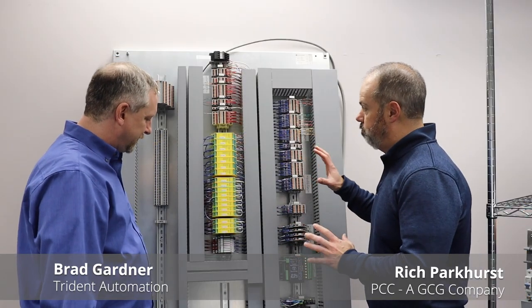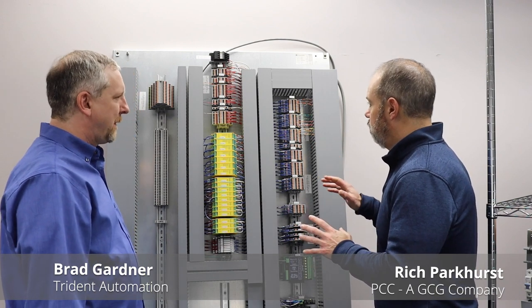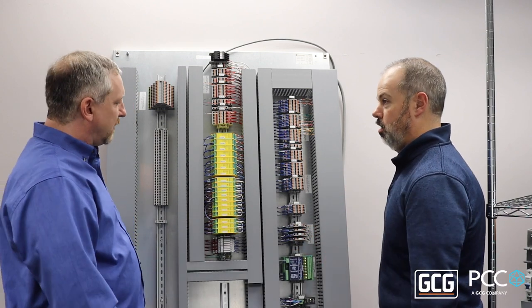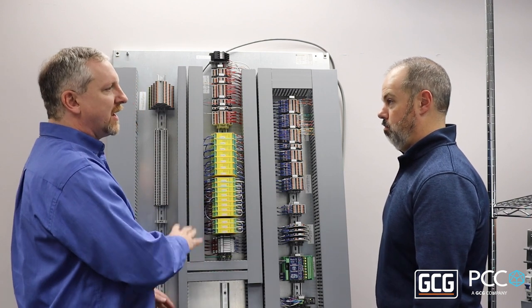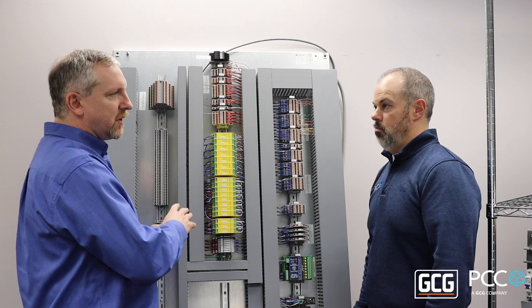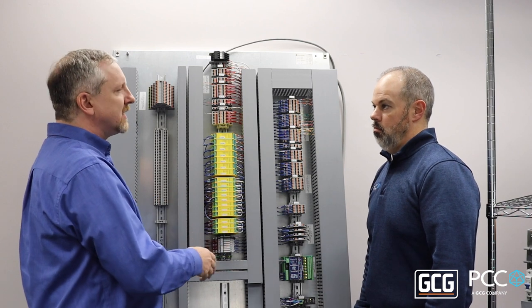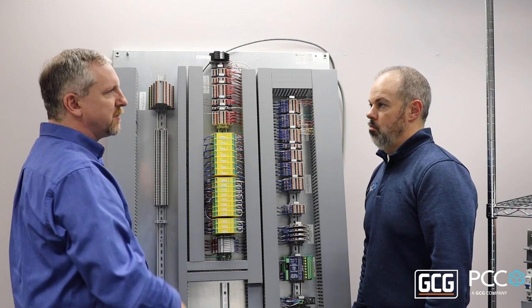Let's take a look at the components of the system. We've got a complete burner management panel here in front of us — this is ready to go to a customer. Our panels are laid out consistently from panel to panel, so even though this is a single-burner panel, if we were to build it for multiple burners, each panel would be laid out identically. Troubleshooting-wise, if something is in one place on one panel, it's going to be in that same place on each of the other panels.